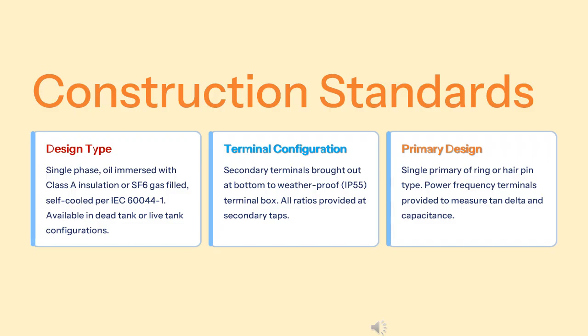Construction standards of EHV CT. Design type, terminal configuration and primary design. In design type section, single phase oil immersed with class A insulation or SF6 gas filled, self-cooled per IEC 60044-1, available in dead tank or live tank configuration. Terminal configuration: secondary terminals brought out at bottom to weatherproof IP55 terminal box. All ratios provided at secondary taps. In primary design section, single primary of ring or hairpin type, power frequency terminals provided to measure tan delta and capacitance.